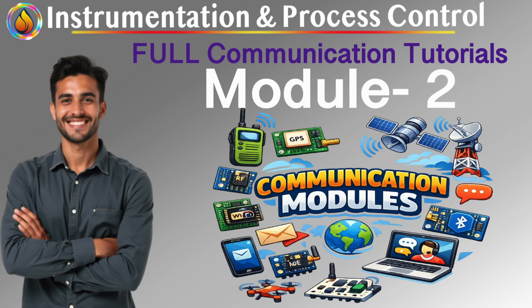Unbalanced signaling. RS232's hidden fragility. RS232 is an unbalanced system. That means one conductor carries the signal, another conductor acts as a common reference, signal ground. The receiver interprets data as the voltage between the signal wire and ground. In a laboratory, it's fine. In a plant, this is where trouble starts, because now your communication depends on ground behaving nicely. And ground, in industrial environments, rarely does.